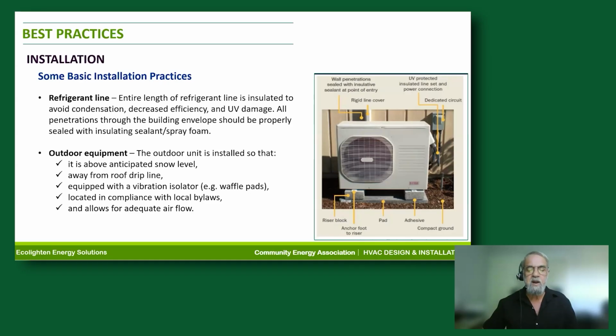As far as installation practices go, particularly with heat pumps, we want to make sure that the entire length of the refrigerant line is insulated to avoid condensation. All penetrations to the building envelope should be sealed with insulating sealant and spray foam. Those are pretty intuitive standards that anybody should expect, but you'd be surprised how often they're not met.